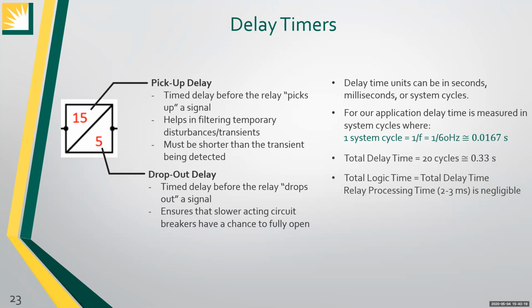The dropout delay, on the other hand, continues to transmit the logical signal it received for the selected amount of time. This ensures that slower acting circuit breakers have enough time to fully switch open before the trip signal is dropped completely. Most modern circuit breakers switch open within 1 to 2 cycles, but some older circuit breakers still in use today have breaking times of up to 4 cycles, which is why we set the dropout delay to 5 cycles.